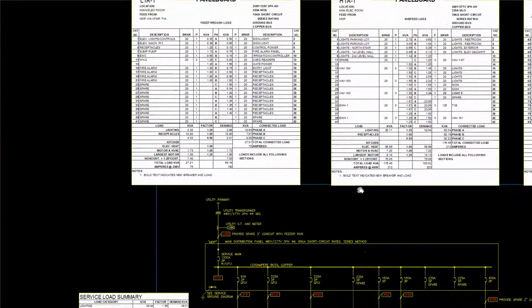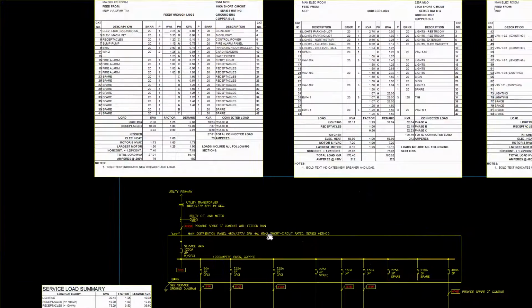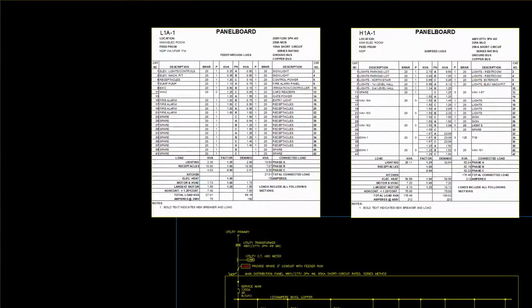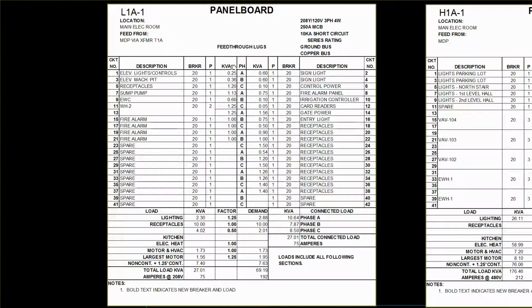So this is L1A1. This happens to be this panel here, and it's a single compartment panel, and it's got all sorts of things. See this 10kA short circuit series rating. It's a 208 volt 120 volt 3-phase 4-wire panel, and you can see all the loads as they're summarized here. Now, with this short circuit current series rating of 10K, actually those are fully rated breakers. Series ratings allow manufacturers to test their 10K breakers, for instance, which are cheaper breakers, with the more expensive breakers, and they put them in series together, and then they can achieve a higher rating that's necessary to accommodate the available fault current.